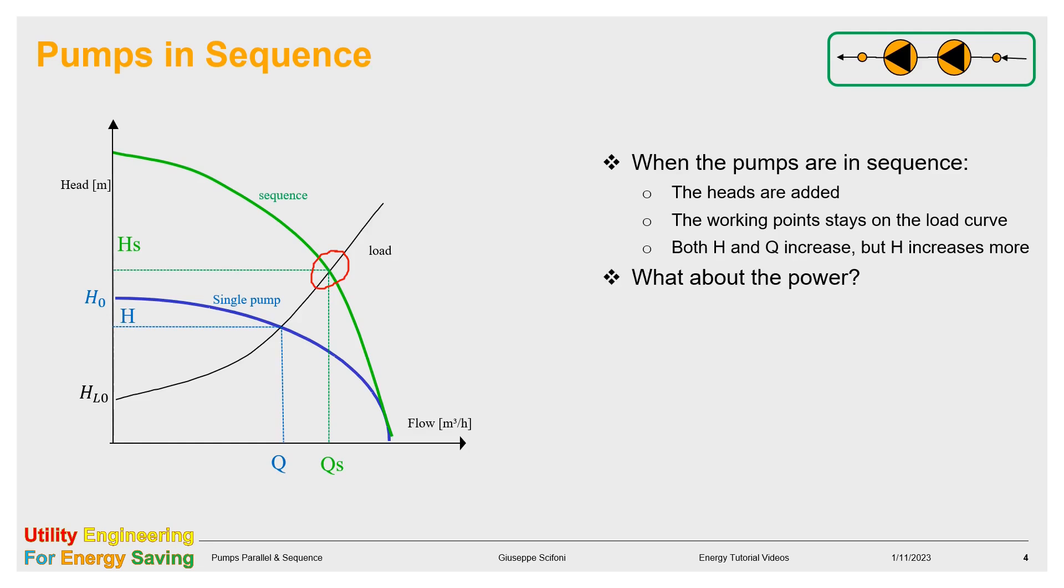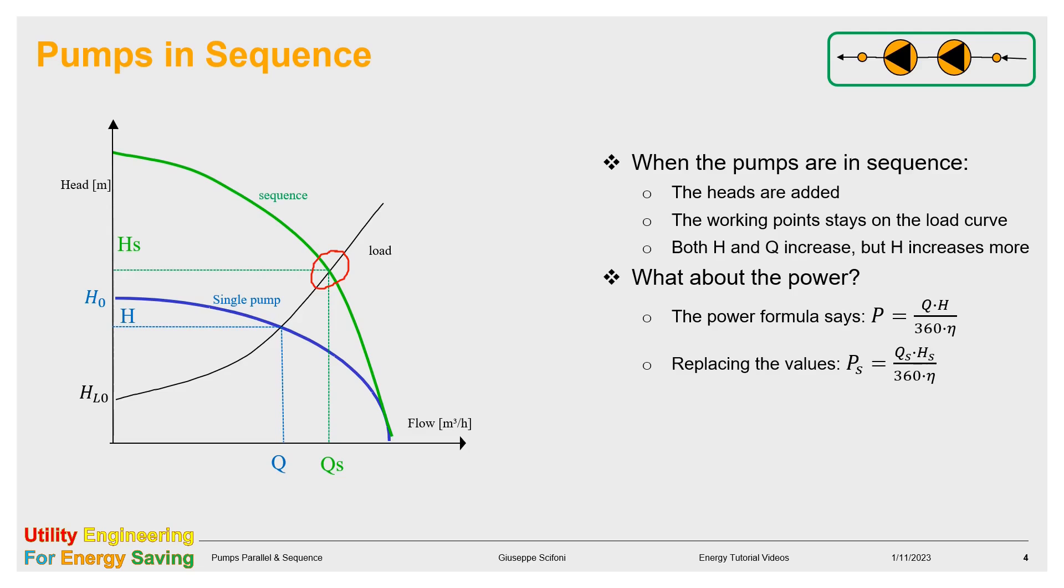The power of the new pumping system is given by the same formula used for the single pump, by replacing the head HS and the flow QS found for the sequence operation, as seen in the previous slide. Normally, the power of the system is less than the sum of the power of the single pumps. This is not a rule, however.